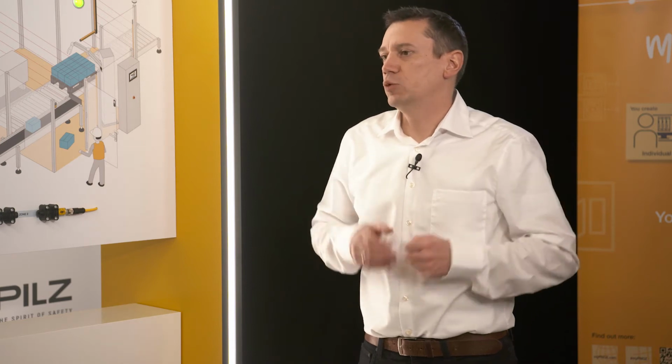We can implement this with myPNOZ. We can implement up to 8 different zones with one system. However, as you have already said, we have this global safety function on the head module, for instance, for the emergency stop, which acts on all these safety areas, on all zones. This allows us to switch off everything at once with the e-stop, or to only switch off the affected zone by means of the specific safety functions per zone, while the unaffected zones can continue to run and thus also continue to produce. Thank you, Steffen.